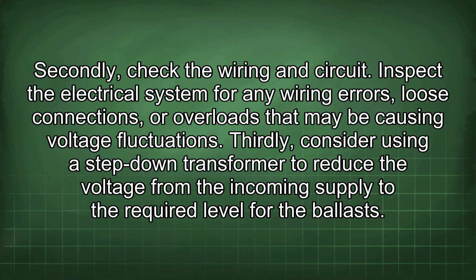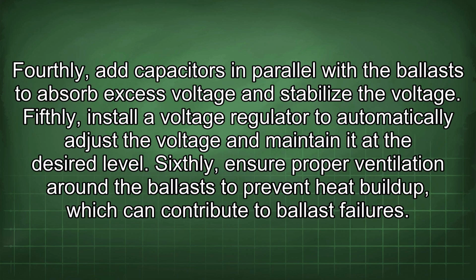Thirdly, consider using a step-down transformer to reduce the voltage from the incoming supply to the required level for the ballasts. Fourthly, add capacitors in parallel with the ballasts to absorb excess voltage and stabilize the voltage. Fifthly, install a voltage regulator to automatically adjust the voltage and maintain it at the desired level. Sixthly, ensure proper ventilation around the ballast to prevent heat buildup, which can contribute to ballast failures.